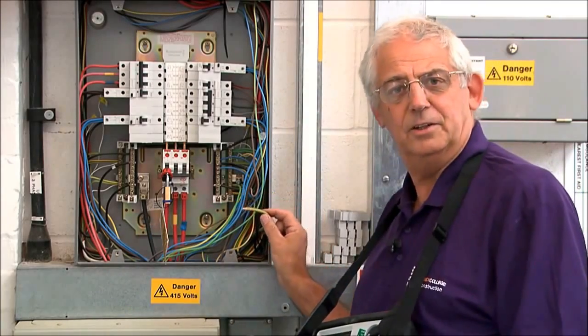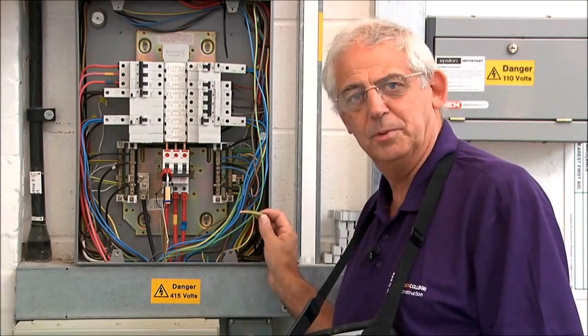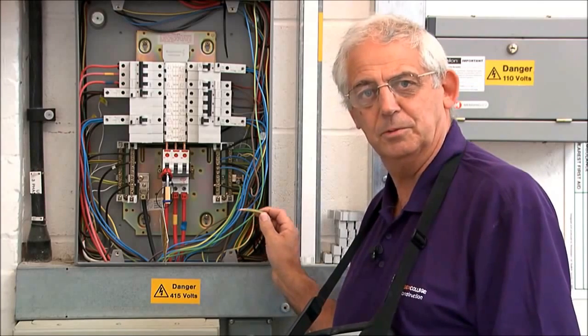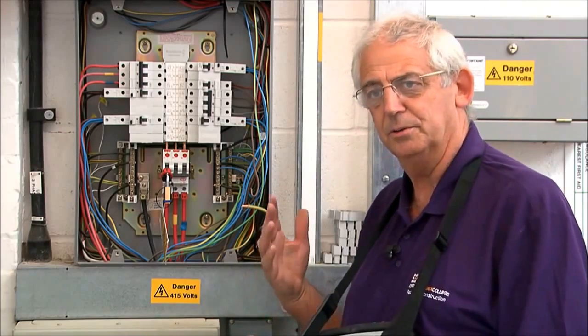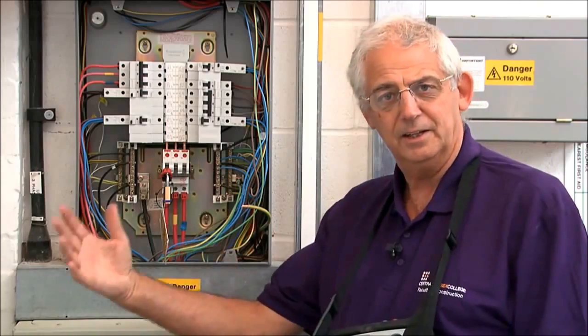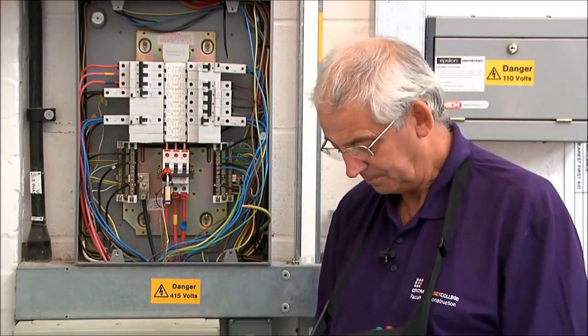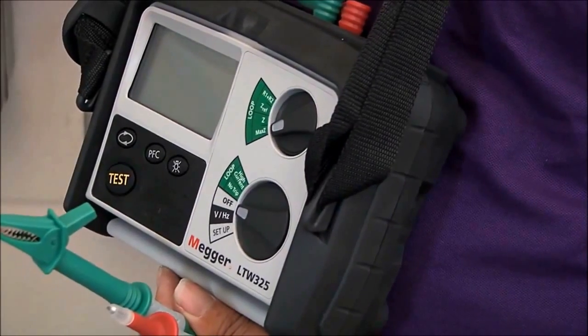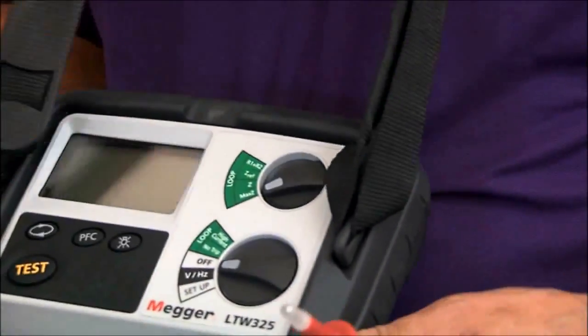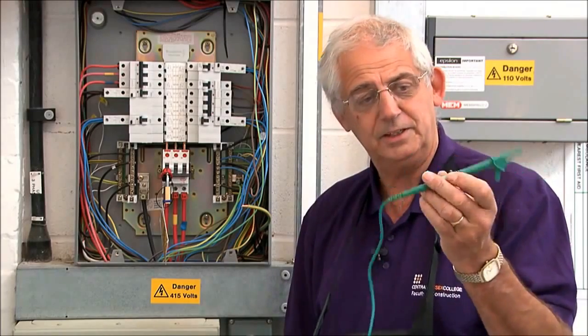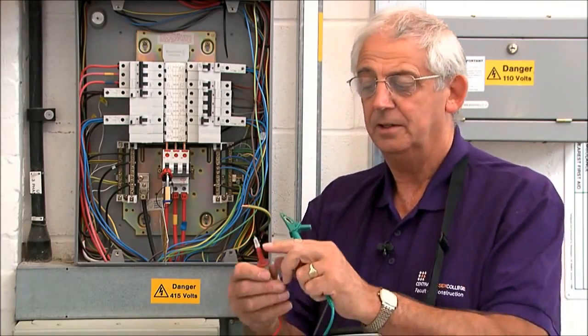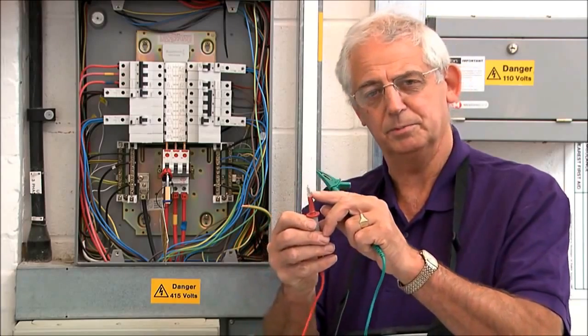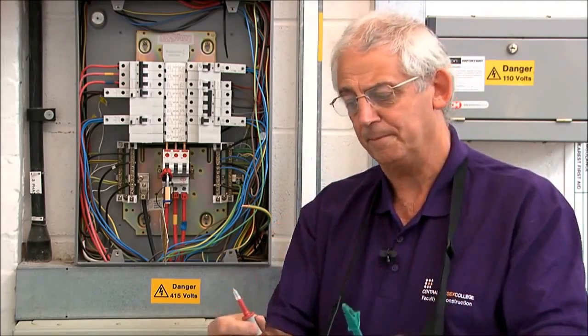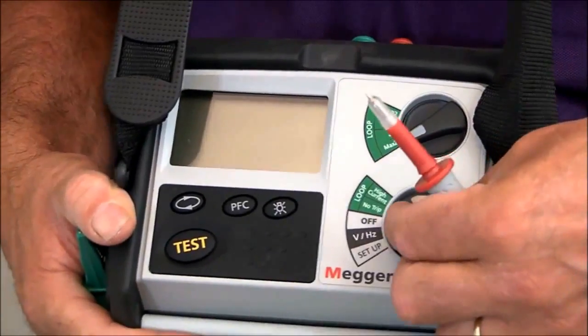I've disconnected the earthing conductor because I don't want any parallel paths. So when I do the test, I just need to know the resistance between here and our supply transformer. To carry out the test, I need an earth fault loop impedance test instrument, okay? With leads to GS38, the contacts need to be covered as much as possible, okay? To do the test is a simple process.